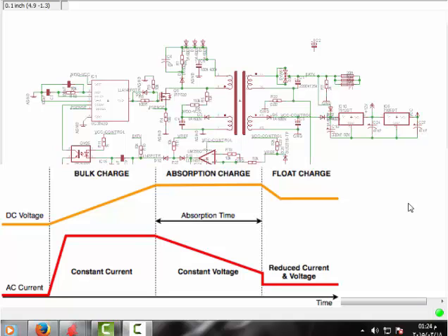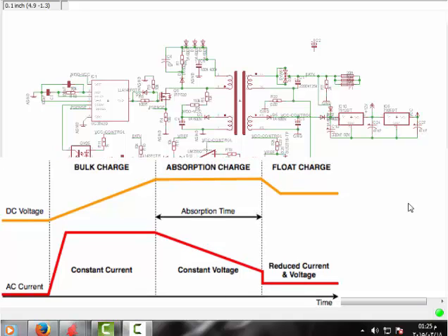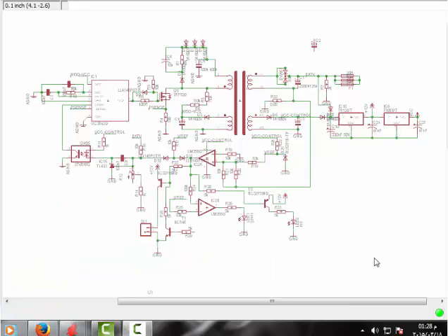If you have a 10 amp hour battery, that means 0.1 amps, and you have to enter the next stage, which is the float charging stage. At this stage, you lower the output voltage from 14.7 to 13.8, and keep the batteries at that level as long as they are connected to the charger. So basically, this is what our charger is going to do.